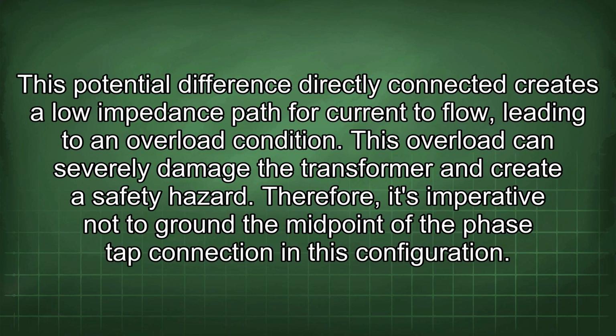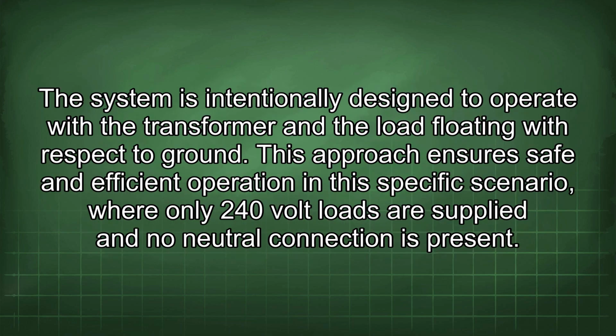This potential difference directly connected creates a low impedance path for current to flow, leading to an overload condition. This overload can severely damage the transformer and create a safety hazard. Therefore, it's imperative not to ground the midpoint of the phase tap connection in this configuration. The system is intentionally designed to operate with the transformer and the load floating with respect to ground. This approach ensures safe and efficient operation in this specific scenario, where only 240 volt loads are supplied and no neutral connection is present.